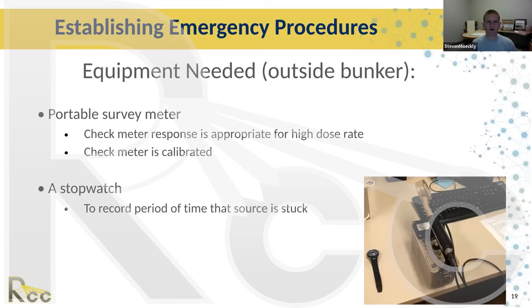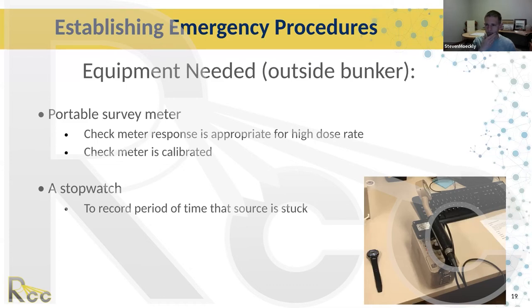Outside the bunker you need a portable survey meter. The one most commonly used is the Ludlum 14C with a 44-9 probe — it doesn't saturate to dead, it's rugged, and has a pancake probe. It's calibrated in millirem per hour. Calibrate it every two years if possible. The cesium check source on the side will help verify function if you can't send it in for calibration. Also keep a stopwatch and a set of backup batteries on hand — the most common meter failure is dead batteries.